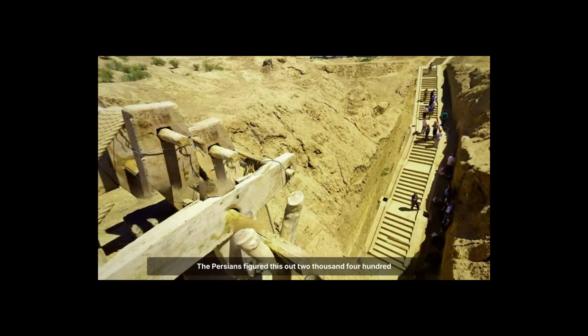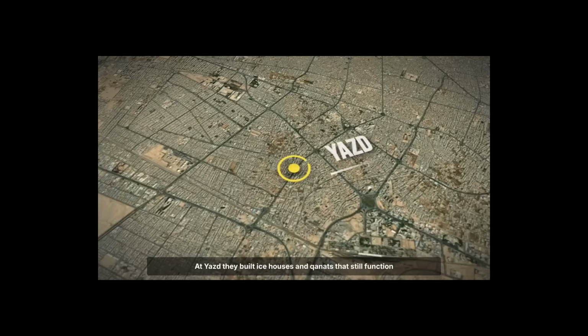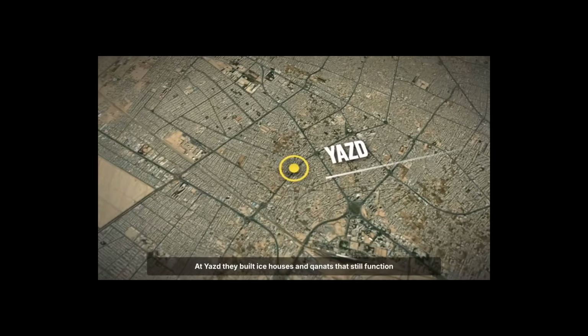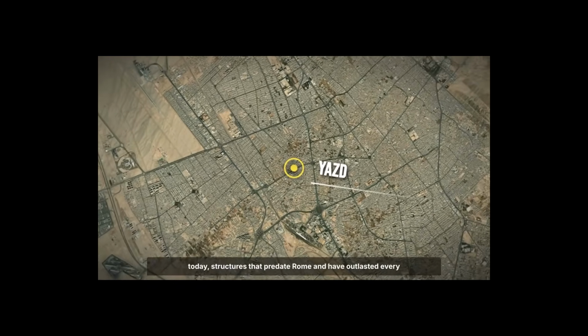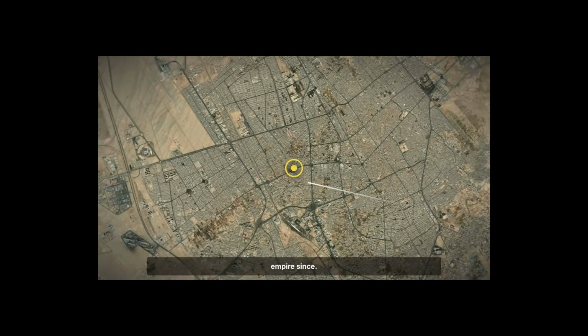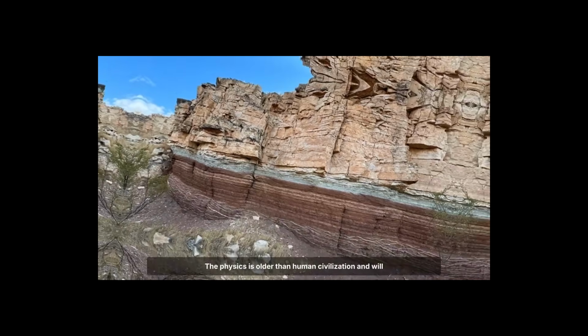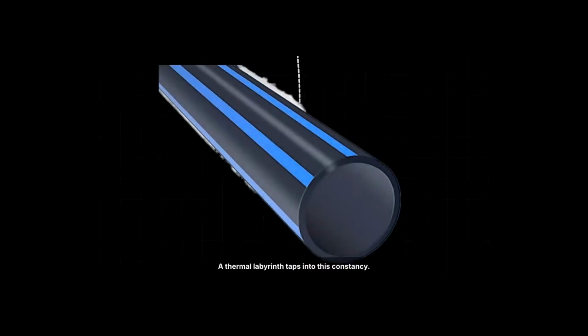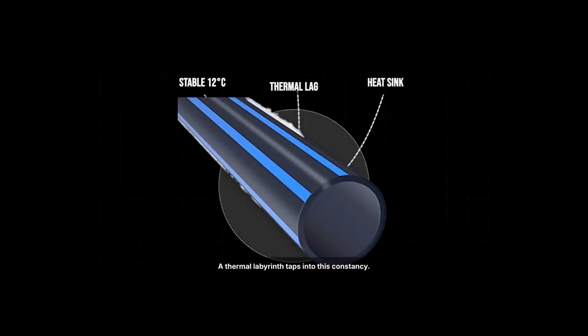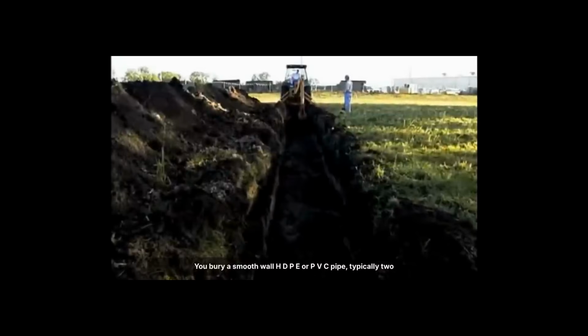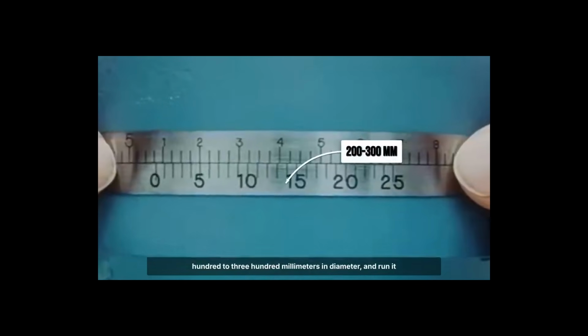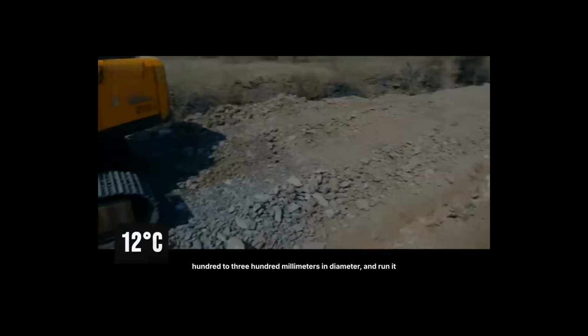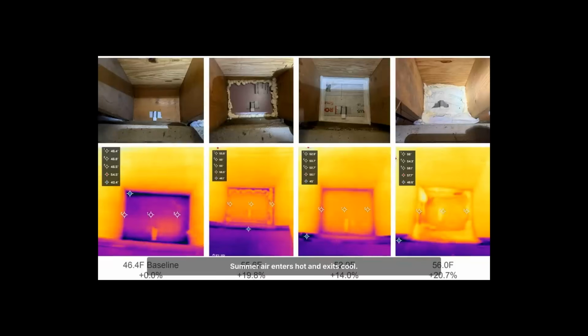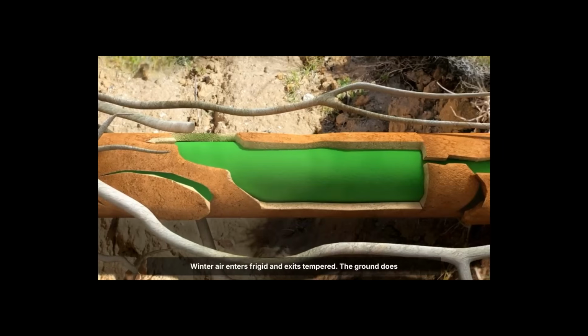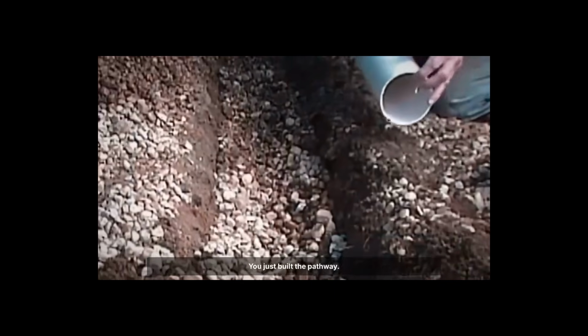The Persians figured this out 2,400 years ago. At Yazd, they built ice houses and qanats that still function today, structures that predate Rome and have outlasted every empire since. The physics is older than human civilization and will outlast whatever comes next. A thermal labyrinth taps into this constancy. You bury a smooth wall HDPE or PVC pipe, typically 200 to 300 millimeters in diameter, and run it 30 to 60 meters through the earth. Summer air enters hot and exits cool. Winter air enters frigid and exits tempered. The ground does the work. You just built the pathway.